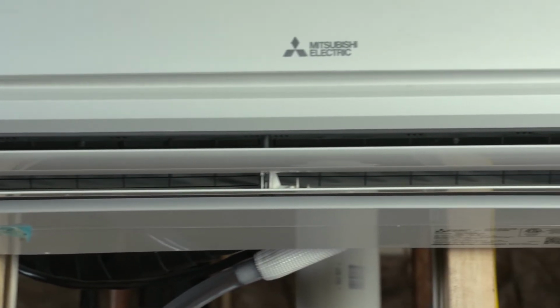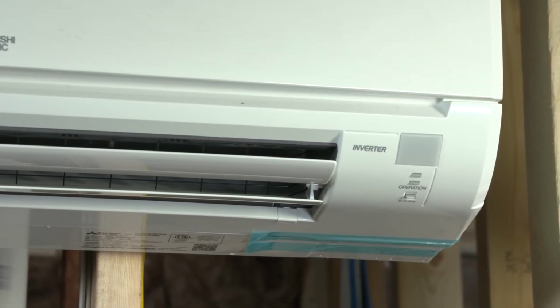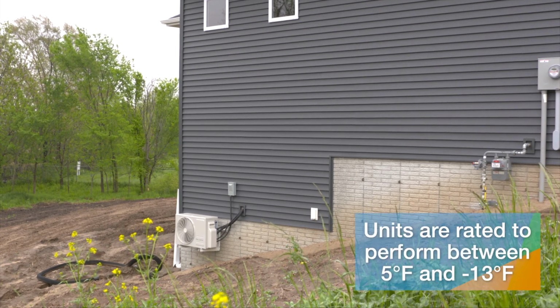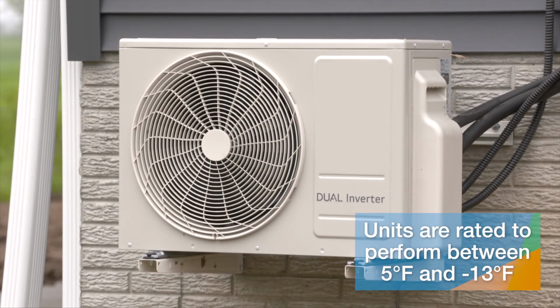Here in the Midwest we have crazy weather, heat waves in summer and Arctic winters. How will mini split heat pumps operate under such extreme conditions? They work wonderfully for cooling, really no issues there. On the heating side, it's something to consider. They rate these units anywhere from about 5 degrees to about negative 13 ambient outdoor, meaning at that temperature the units perform at 100% of their design capacity. As it gets colder, they have to work a lot harder to produce that heat, since there's just not as much heat left in the air to pull from. So if you have a space like a garage, or somewhere with water or things that can be harmed by cold, you still need to have a backup heat source available for when it gets into those very cold polar vortex conditions.